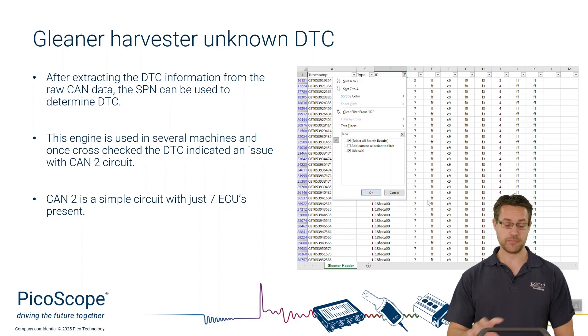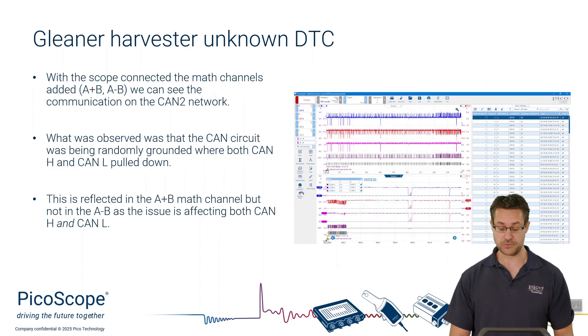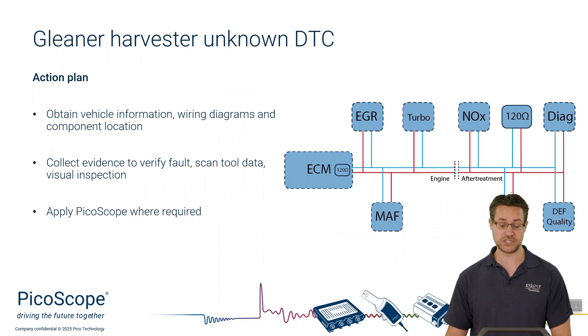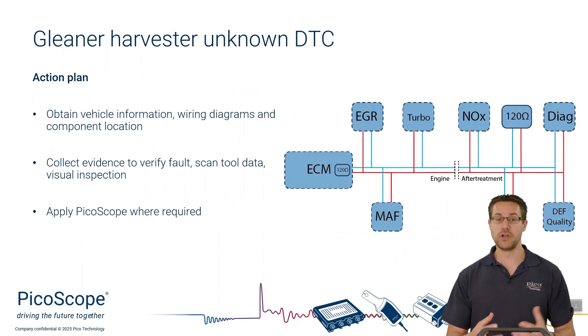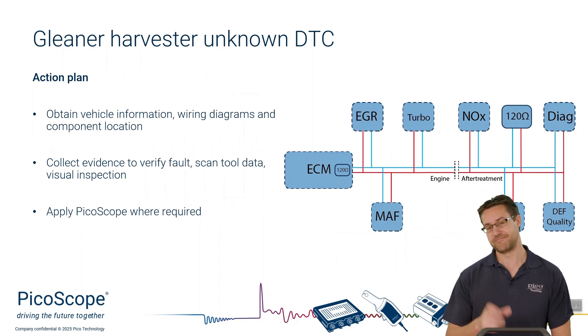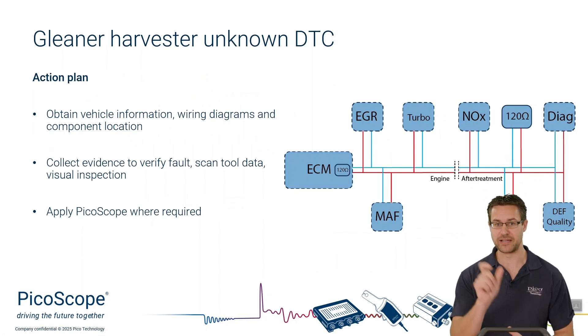CAN2 is a simple engine control network comprising just seven ECUs. The topology includes the engine ECU, an EGR valve, mass air flow, turbocharger, two NOx sensors, a diesel exhaust fluid quality sensor, and access to the diagnostic port. With a lot of off-highway machinery, the terminating resistor is quite often in the engine ECU, but they can also be external - sometimes they look like a blanking plug with a resistor inside, so keep an eye out for those.